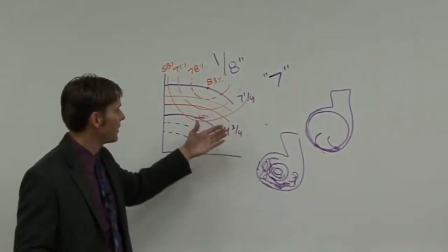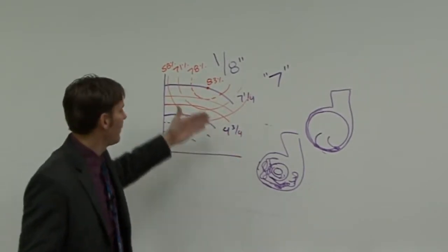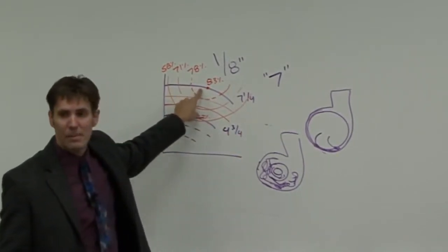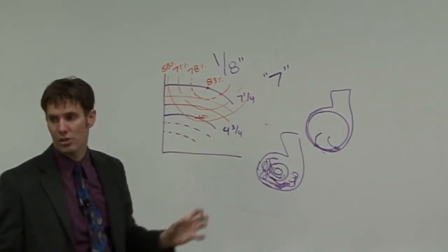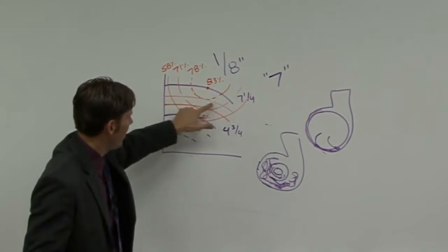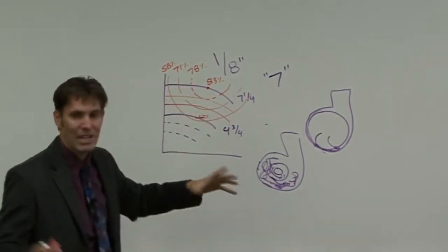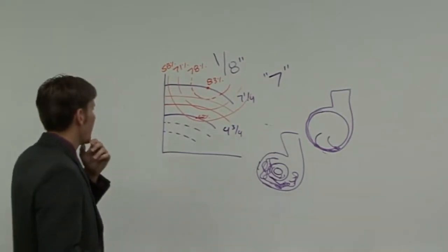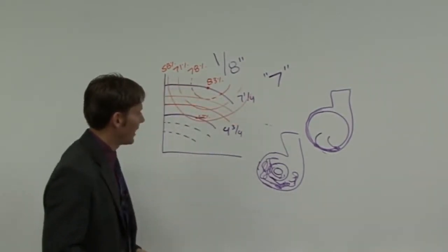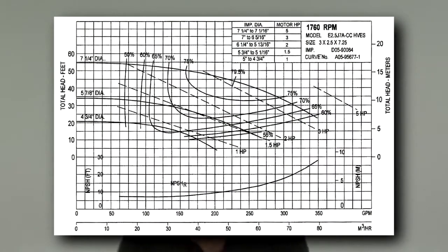My comeback to that is, well, just make sure that you're doing your engineering right. If you can, you want the pump to operate on this maximum curve because it's going to be the most efficient curve. I'd much rather operate on this curve than this curve or this curve or this curve because I'm going to be more efficient. Okay? So that's what we're looking at with our efficiency lines. When you look at this curve, their best efficiency point is approximately 80%. So it's marked there at 79.5 if I'm at my best efficiency point on my maximum trim. But on my minimum trim, my best efficiency is probably going to be close to 66%.